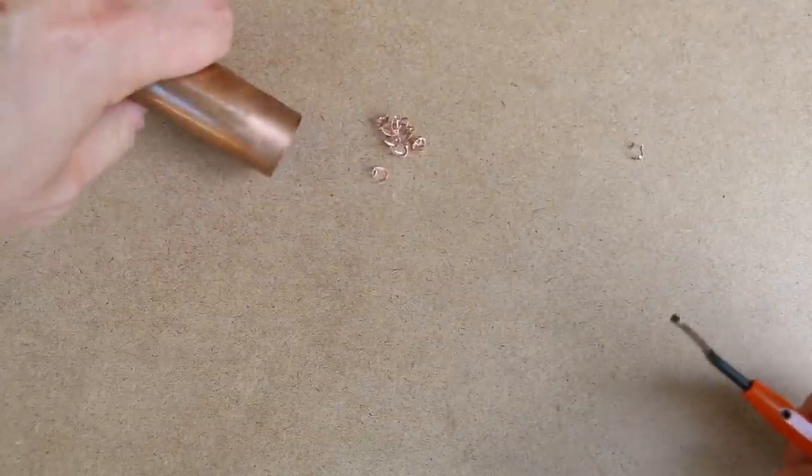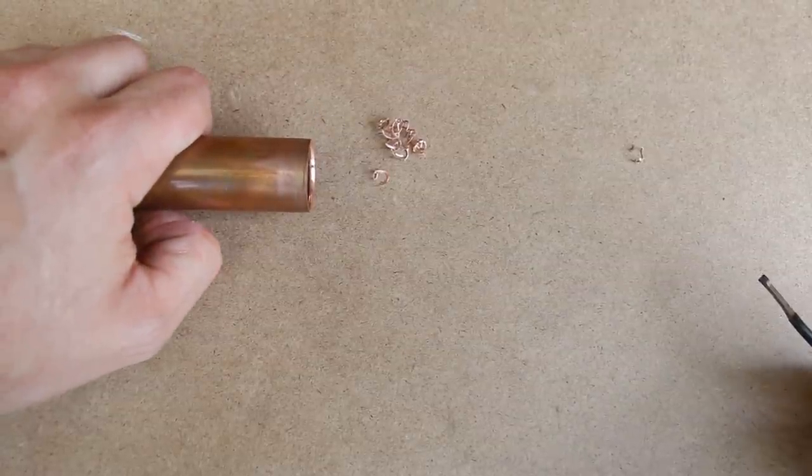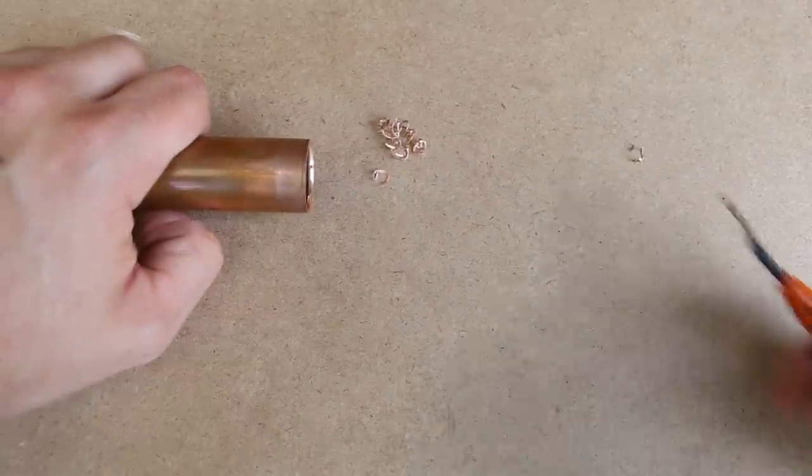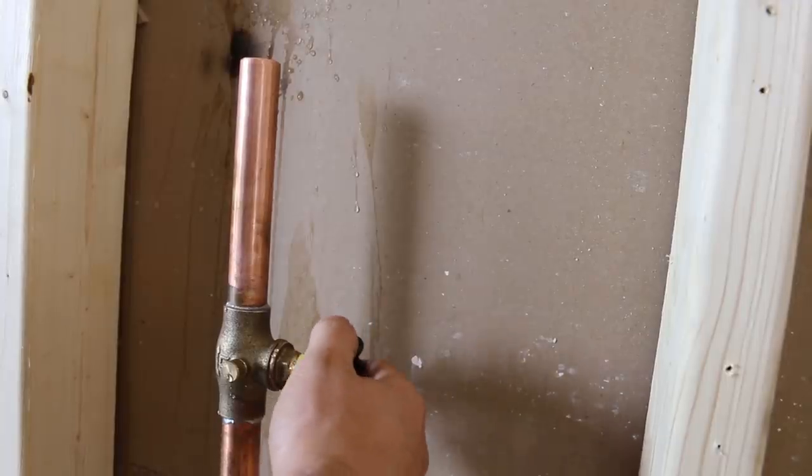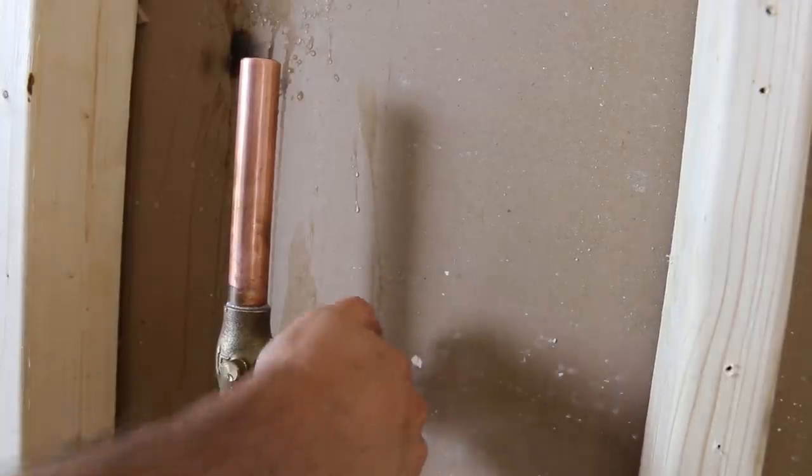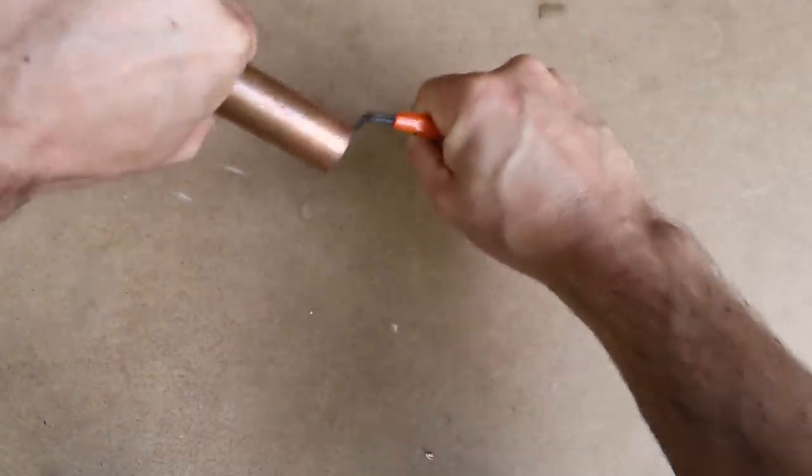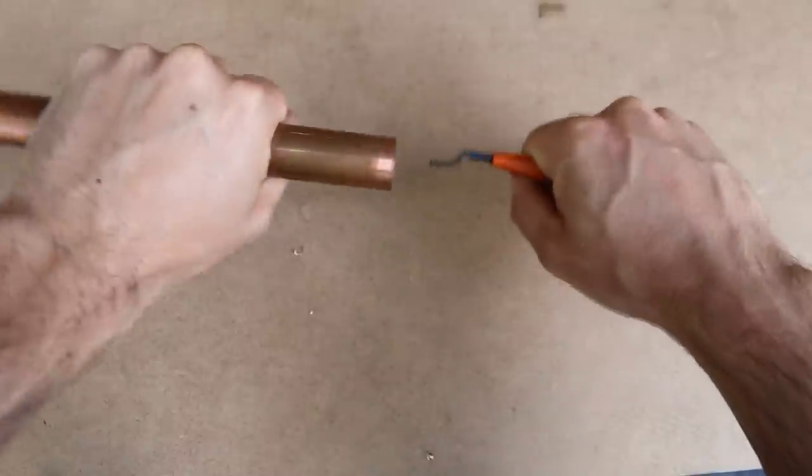Also, you want to make sure that the shavings aren't going inside the pipe you're deburring, because they could clog small orifices. So always purge your lines once you're done, or better yet, if you can, deburr the pipe upside down so the filings fall out and don't go in the system.